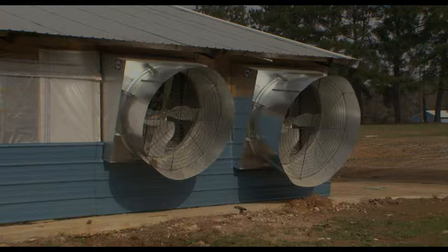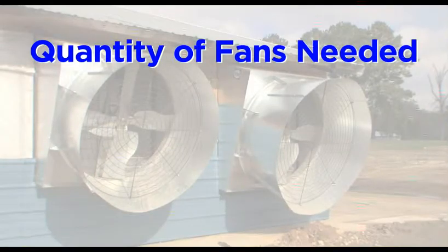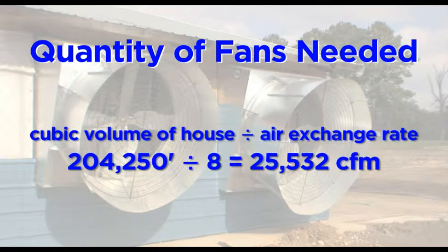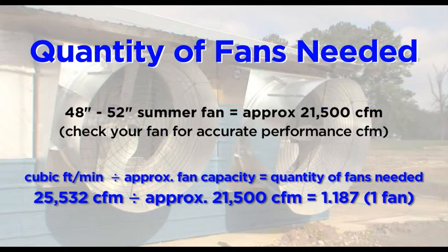First we need to determine the number of fans needed at actual working pressure — first stage. Fan volume equals 1 air exchange every 8 minutes during the first stage of minimum ventilation, to run on a cycle timer and temperature override. To determine the number of fans needed, take the cubic volume of the house and divide by 8, the air exchange rate every 8 minutes. Then divide by the volume of air one summer fan can displace. In this example, one summer fan can displace 21,500 cubic feet per minute.